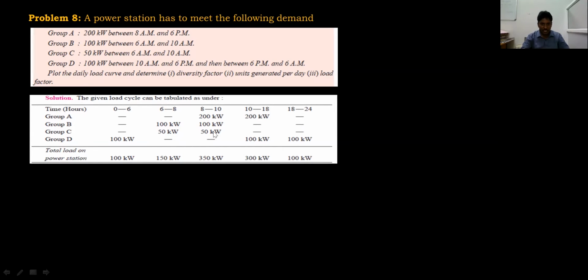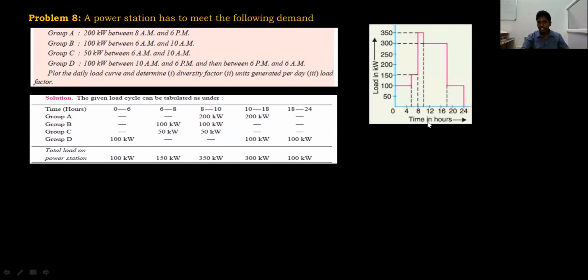If you have this information, you can easily draw the load curve between time and kilowatt demand. Here time in hours, 0 to 24, is given, as well as the load in kilowatts. We can draw the graph here. Between 0 to 6, what is the load? 100 kilowatts. Between 6 and 8, what is the load? 150. In the same way, we continue with the further information and draw the load curve. And finally, what is the peak point? The peak point here, the maximum demand, is 350. Therefore, the maximum demand on the power station is 350.